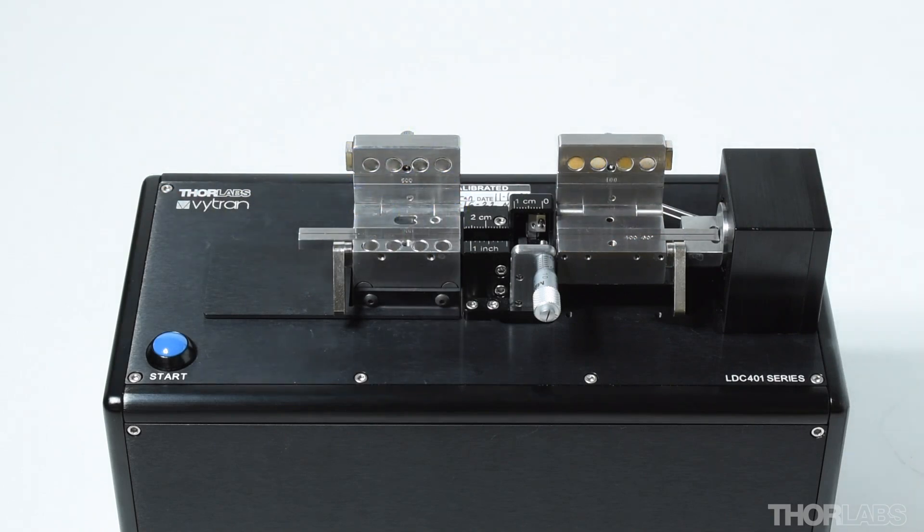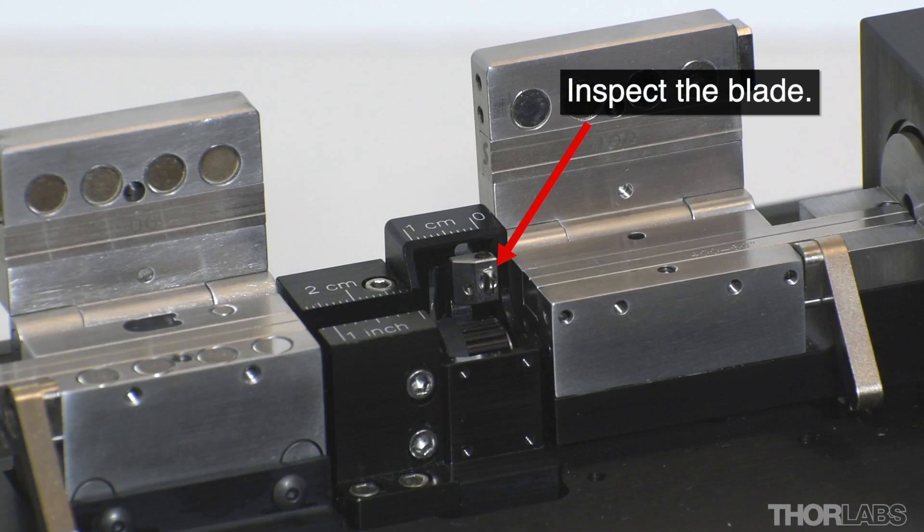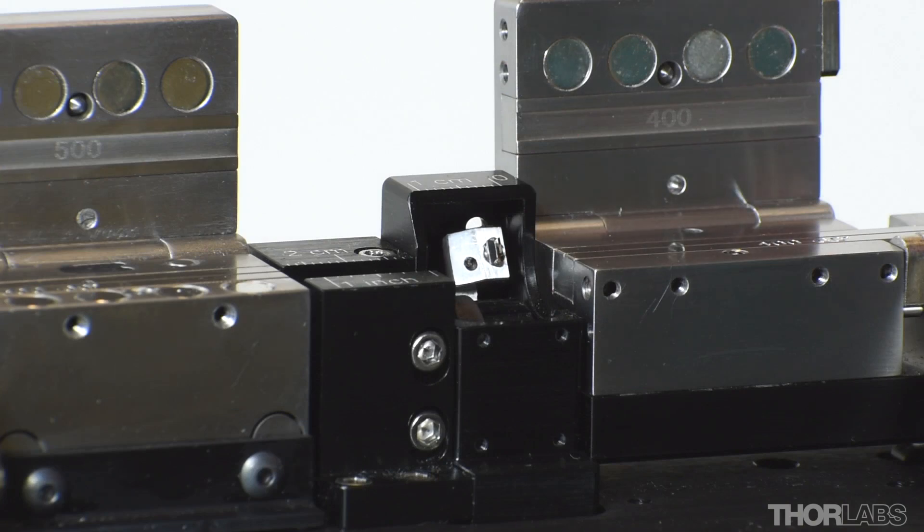If the cleave quality is still sub-optimal after cleaning the inserts, next inspect the blade. Inspect the blade for cleanliness and any signs of damage using a magnifying eye loupe. To inspect the blade visually, it will need to be moved to its service position.